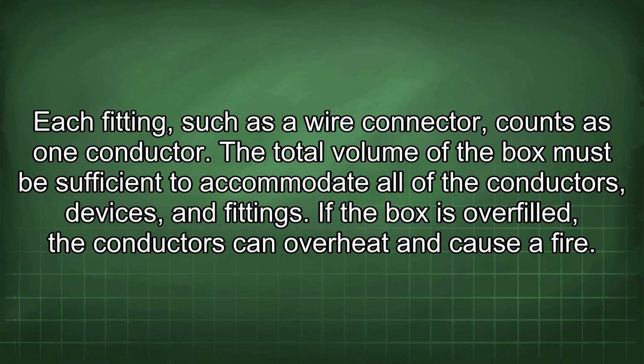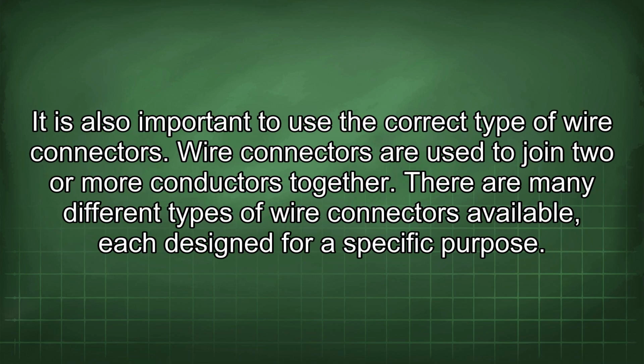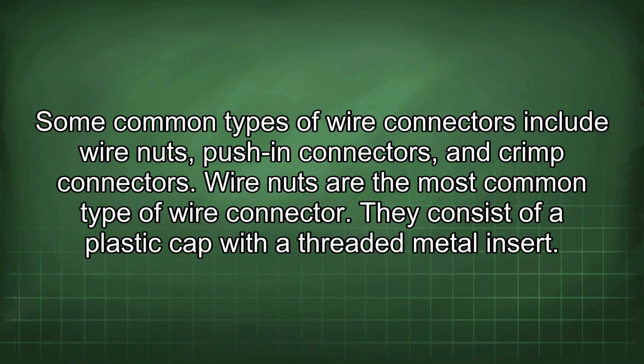If the box is overfilled, the conductors can overheat and cause a fire. It is also important to use the correct type of wire connectors. Wire connectors are used to join two or more conductors together. There are many different types of wire connectors available, each designed for a specific purpose. Some common types of wire connectors include wire nuts, push-in connectors, and crimp connectors.